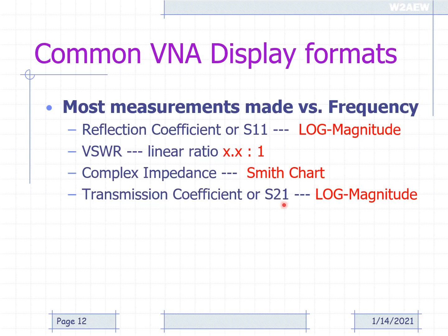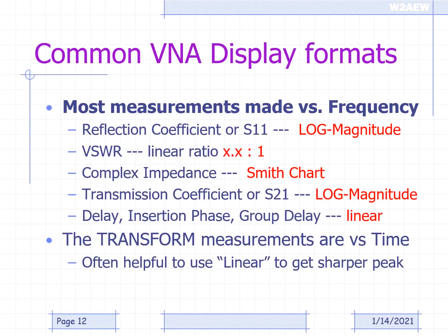Complex impedance is most often displayed on a Smith chart. You do have options of displaying real and imaginary components versus frequency, but a Smith chart is a more common way to actually take a look at that impedance. And then the transmission coefficient, or the gain or loss through a device, is again typically represented by the log magnitude response. I've got 10 dB of gain, 5 dB of loss, etc. And then the insertion delay, the phase, group delay, things like that are typically on a linear scale. And of course, there's a time domain transform measurement that allows you to make measurements versus time, which are typically used to measure the distance to fault or the length of a cable. It's typically measuring the reflection coefficient, but if you change it to linear, you actually get a sharper peak in the response. It makes it a little bit easier to get a precise measurement of delay or distance.